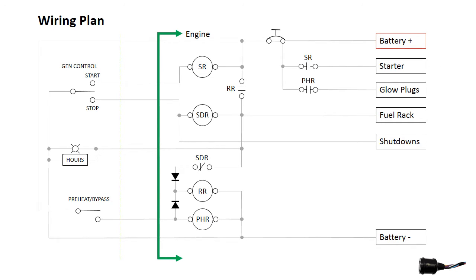The generator's electrical junction box contains the DC logic for engine operation. A circuit breaker protects the control system and the wires to the control panel. The preheat relay controls power to the glow plugs for cold engine starts. The start relay controls power to the starter solenoid.